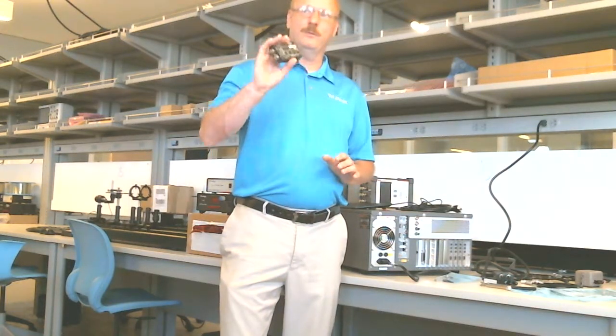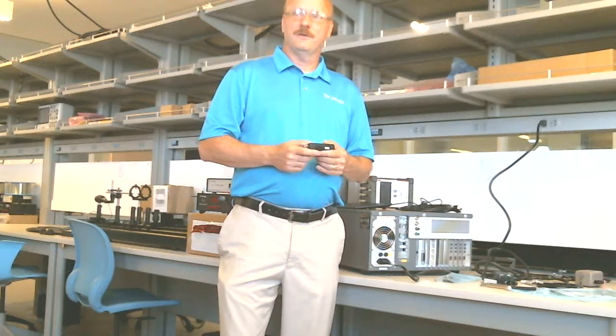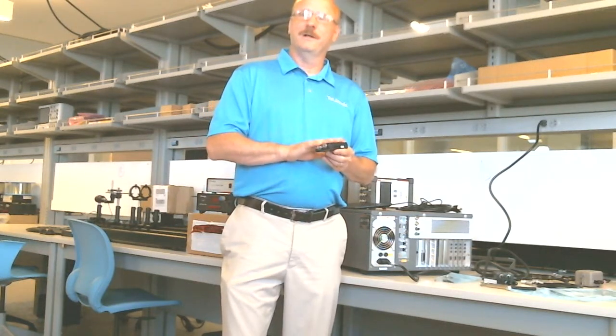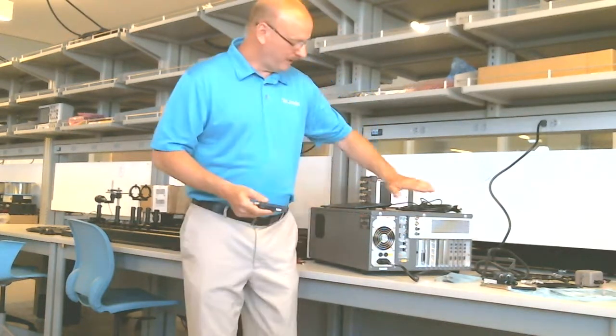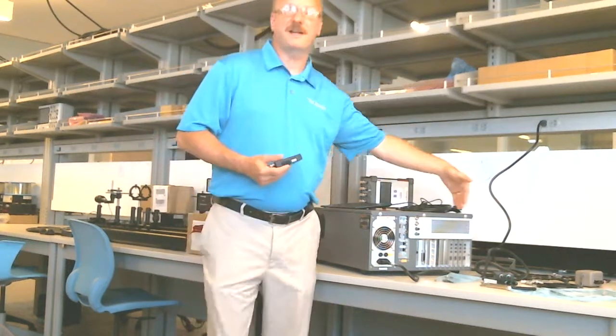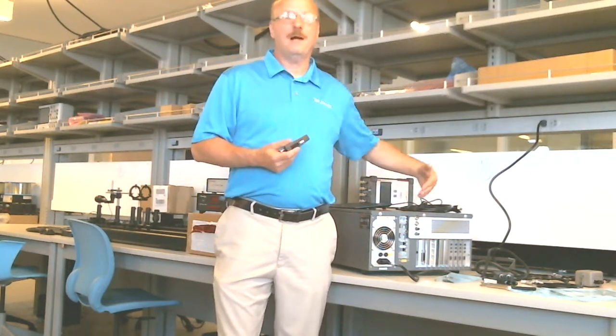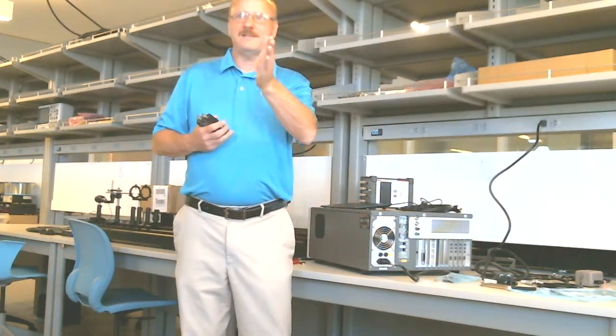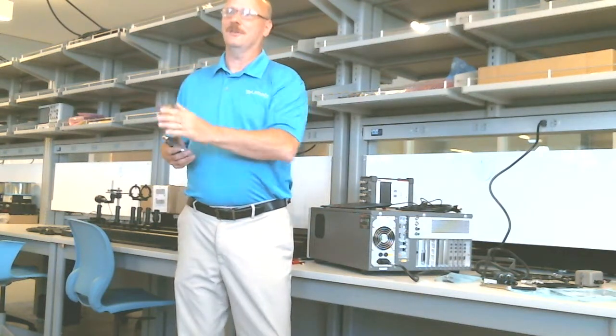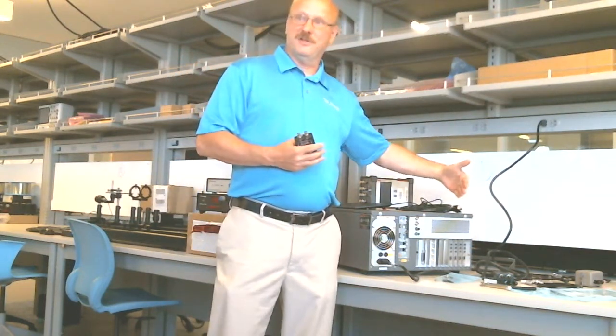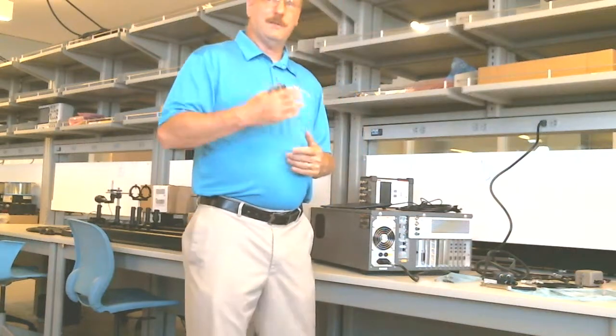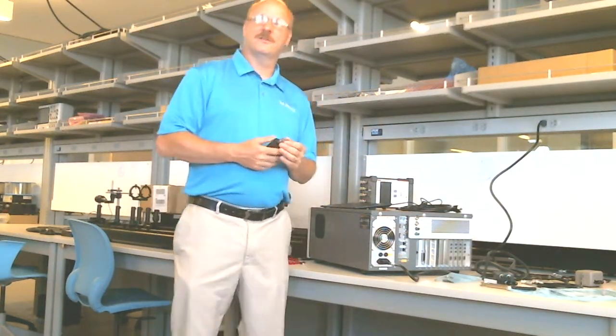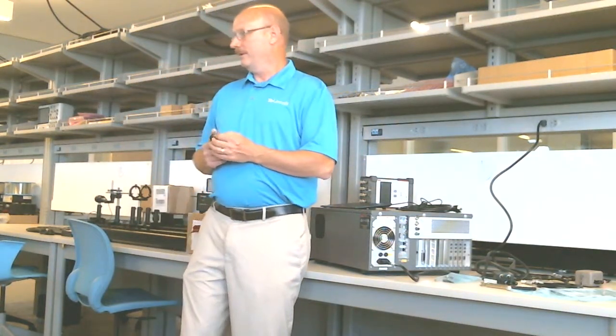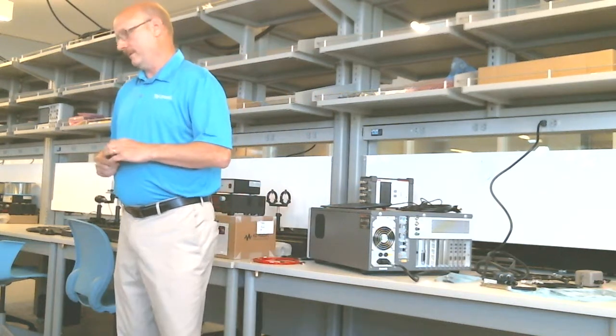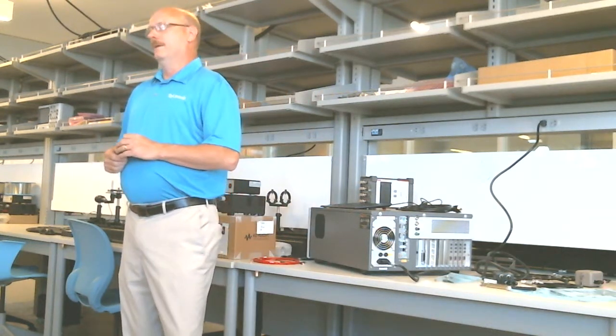It's calibrated with that SMU. There's a preamplifier in here that has to be calibrated with the channel, and the SMUs have to stay in the slot they're in as well. You can't move them around because the different slots in the backplane have different capacitance, so they're calibrated in position. Okay, so I know calibration was one of your concerns. So if they were to add an SMU or an LCR, they would have to be recalibrated? Maybe.